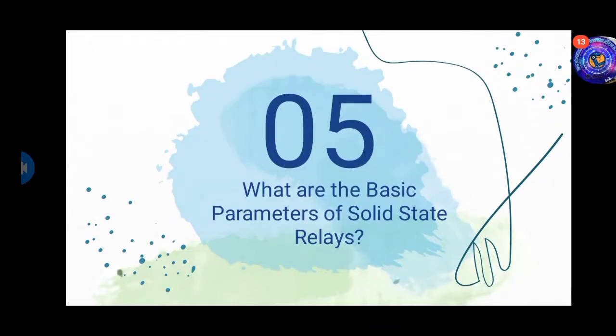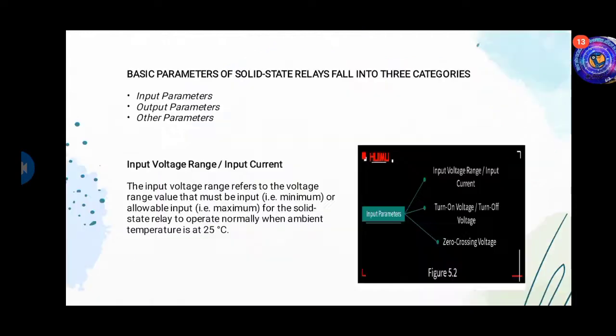What are the basic parameters of a solid state relay? The basic parameters of a solid state relay fall into three categories. The first category is input parameters, the second is output parameters, and the third is other parameters. Input voltage range or input current: the input voltage range refers to the range of values, either minimum or maximum allowable input, that must be applied for the solid state relay to operate normally when the ambient temperature is 25 degrees Celsius.